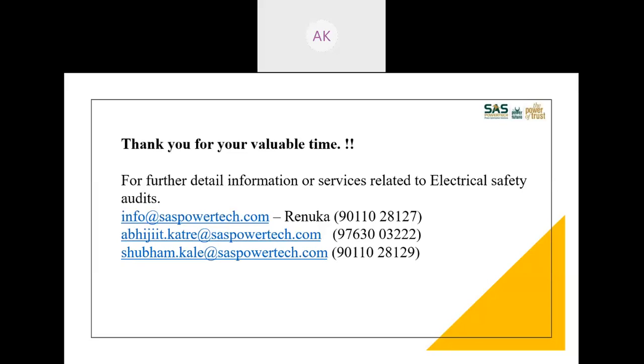Does intelligent electrical documentation help to comply with safety standards? Definitely. The moment you have all those calculations made, you have a reason for every act you are doing in actual implementation. And at least as far as ETAP is concerned, what I know is every calculation is done based on some standard. So if I do short circuit analysis using ETAP, it is done to comply with IEC 60909. If I do arc flash, it is done to comply with IEEE 1584. So the results and recommendations which come out of that study and documentation are guiding you to adhere to a particular standard. So you can say that if you follow those guidelines, you are complying with those standards.